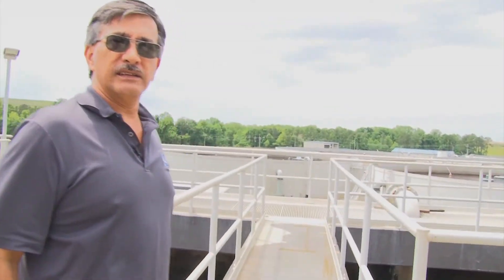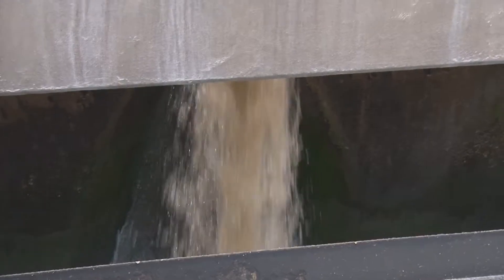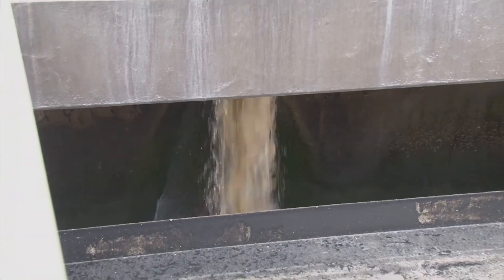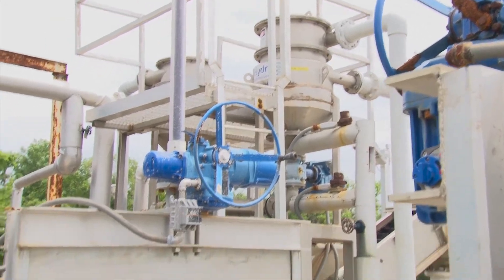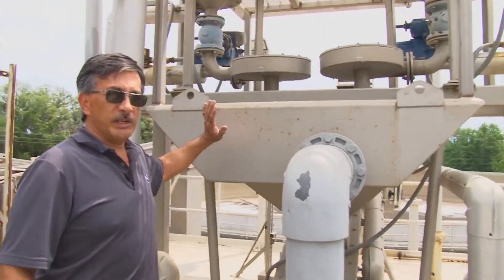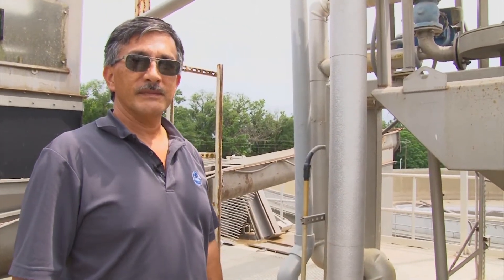This is where the water actually comes into the plant — comes through the screens. These are grit accumulators. It slows the water down to less than two feet per second and drops any heavy solids out of the water, which is then picked up at the bottom and taken over to the teacups on top. The water is slowed down again and drops out the solids into another accumulator, which is then picked up by what we call a grit snail — because it moves so slow — and taken out down a pipe to a waiting bin where it gets thrown away.